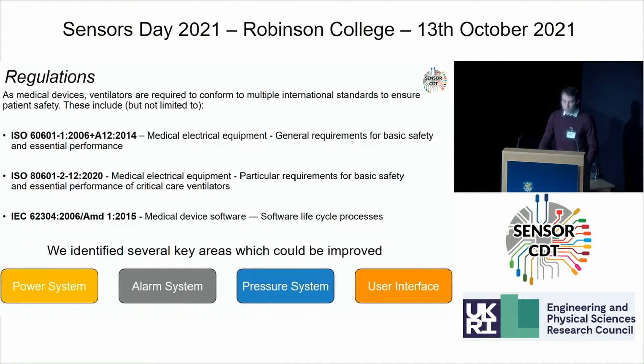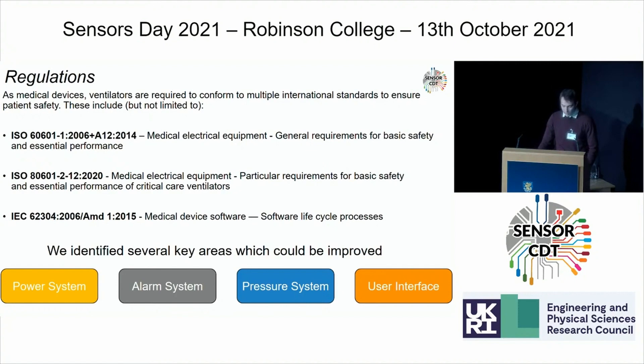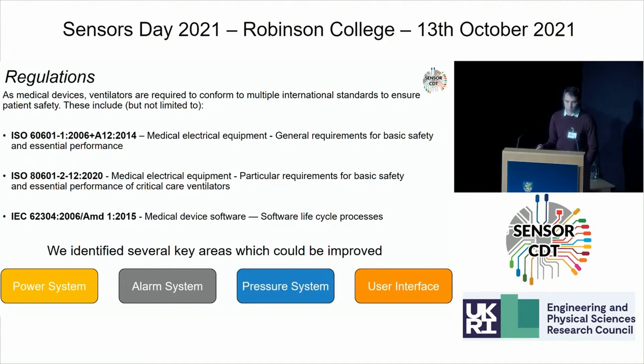It was quite difficult just to get the information before we could make it ready to be put online. The final stages were getting all the design files and writing READMEs for the different materials to help make it more open and reproducible. As part of documentation, we also looked into the medical regulations that would apply to the ventilator. While we didn't have time to make the ventilator fully regulatory-appropriate, we identified several key areas to improve — the power system, alarm system, pressure system, and user interface — which helped inform the tech team in their work.